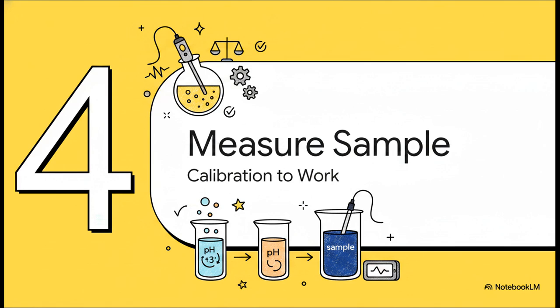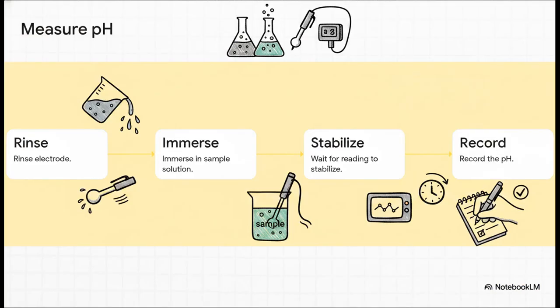Section 4. Sample measurement. Putting calibration to work. This is exactly where all your careful setup actually pays off. You're going to apply the exact same rigorous micro-routine we just learned directly to your unknown sample. Rinse the electrode to ensure zero buffer solution is carried over, immerse it into your sample solution, and once more, wait for a rock-solid reading before recording your data. Because you took the time to do a full 3-point calibration, you can trust this final number implicitly.